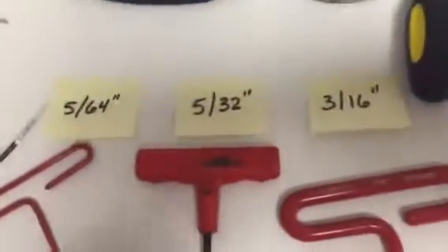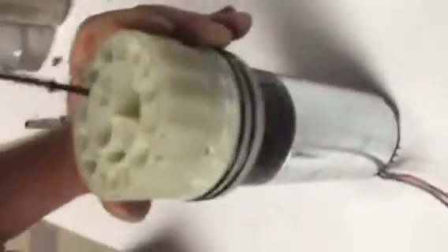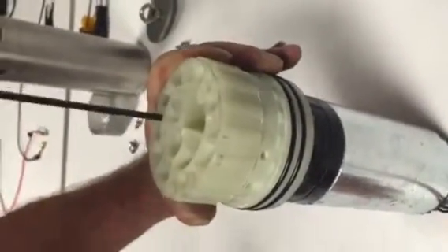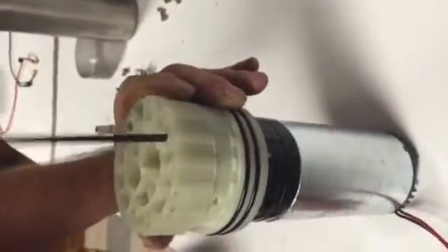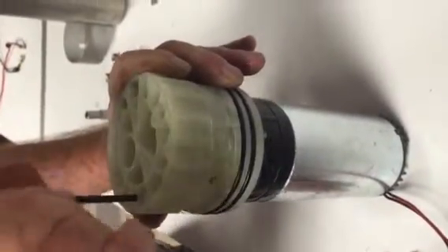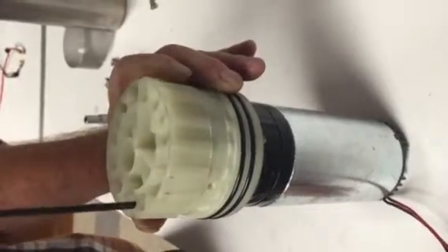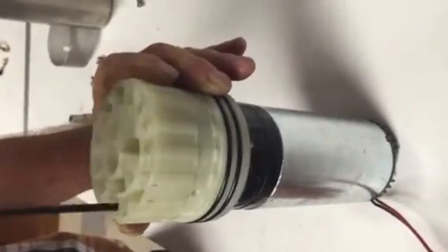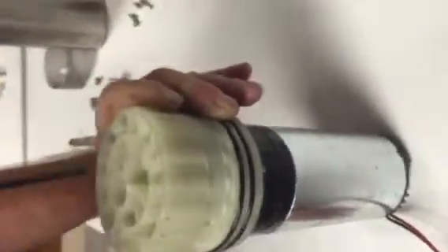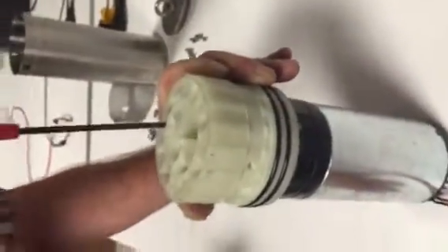But you see where we're placing the hex screws, one there, and we'll place the third in the center, right there. With the 5/32 of an inch Allen, we're going to hand tighten these. As you're tightening them down, you want to tighten evenly, across, or cross tightening. These are quite a bit of thread, so you will be doing this for a little bit. But you can see we are trying to cross tighten to have an even fix.